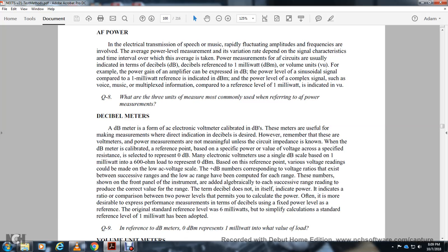The decibel numbers can be added algebraically across successive voltage ranges, as the range numbers are shown on the front panel of the instrument. The decibel does not directly indicate power but indicates the ratio between two power levels. It is often more desirable to express performance measurements in decibels with a fixed power level as a reference. The original standard reference level was 6 milliwatts, but the simplified standard reference level of 1 milliwatt has since been adopted.